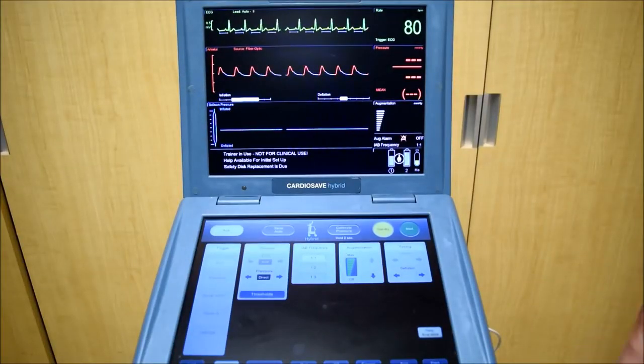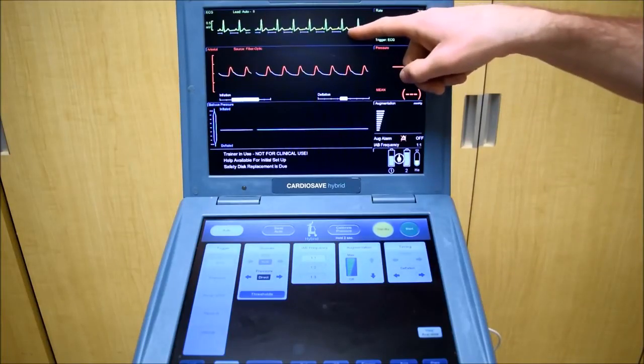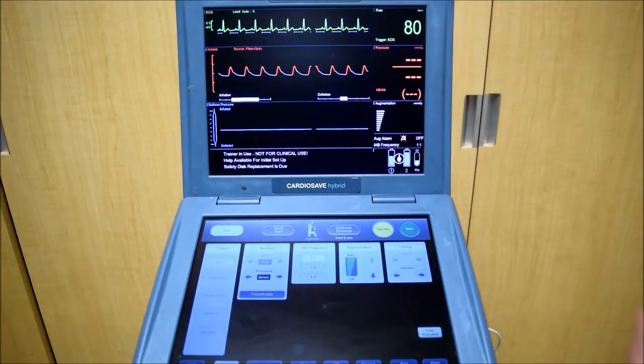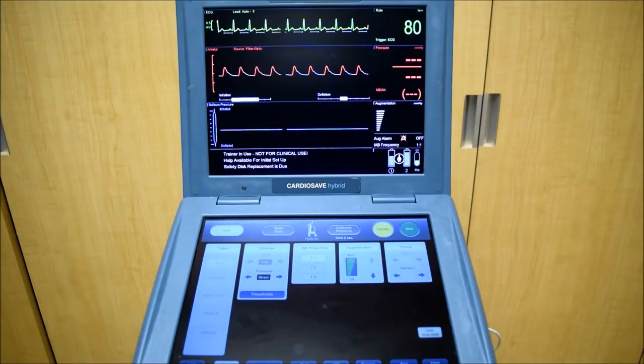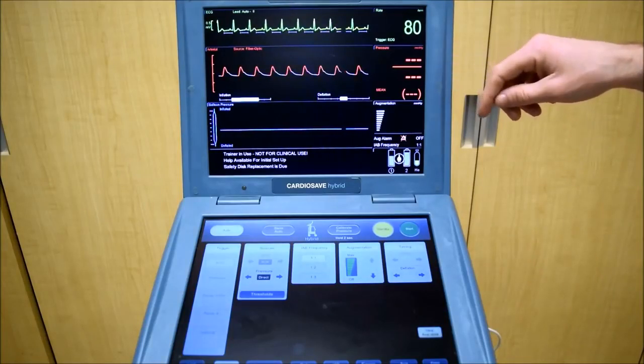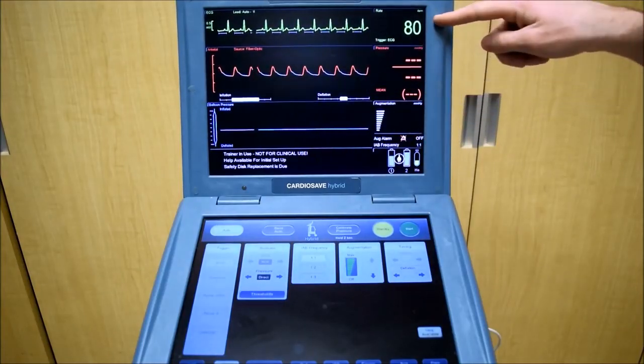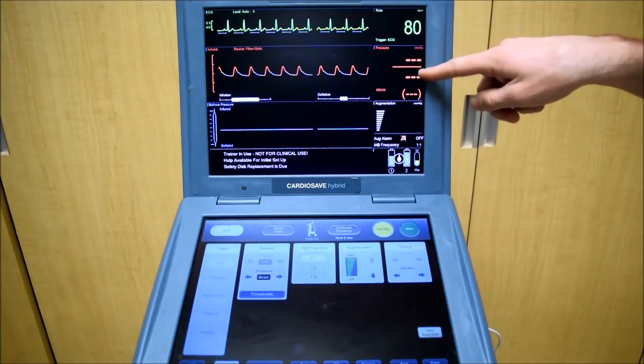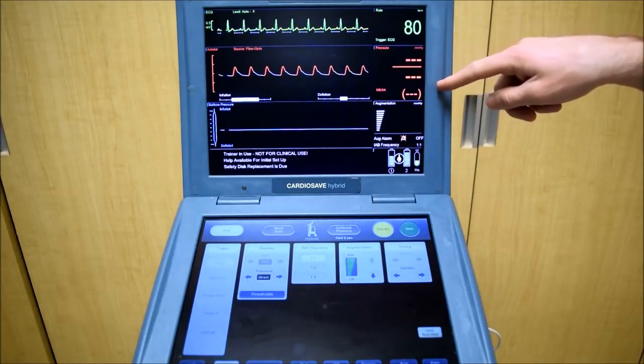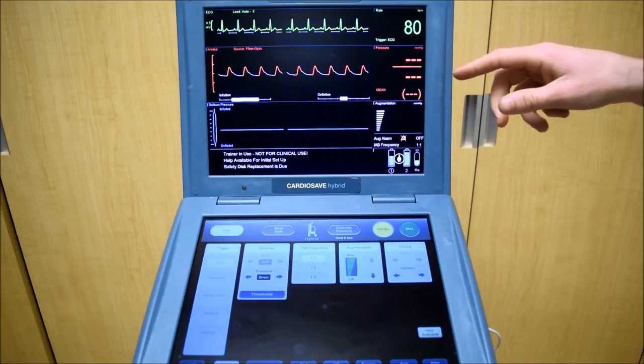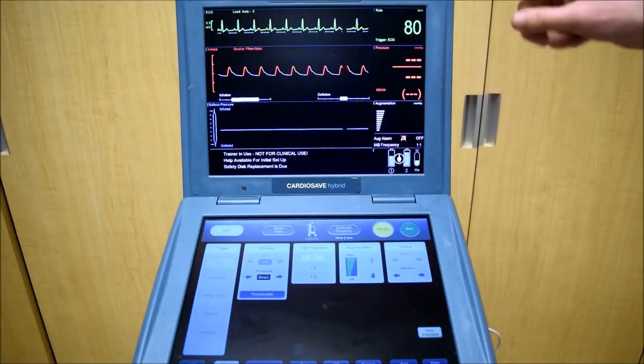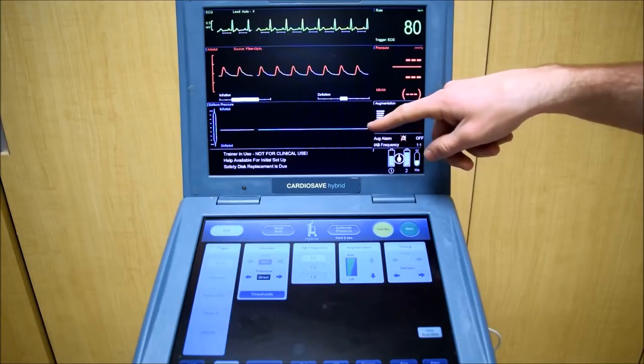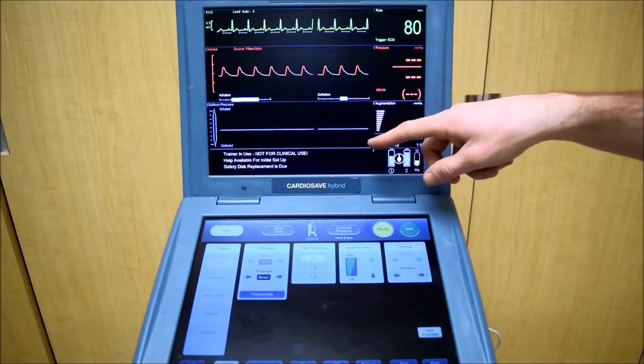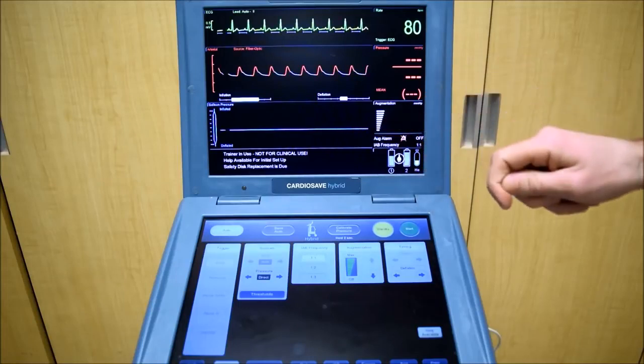Now that we have the balloon pump powered on and our ECG and pressure leads attached, we can see our EKG trace and our pressure trace. Before we get started, I want to run through the layout of the two screens. In the upper screen, you'll notice our two traces, our beats per minute, and this will read our diastolic and systolic pressures after we calibrate the pressure transducer. This lower line represents the augmentation of the balloon, or the balloon inflation and deflation.